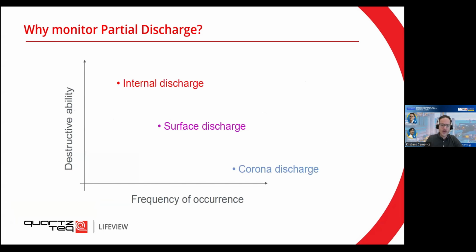So why do we need to monitor? The main reason here, as you saw before, is that for example the surface discharges, it's sometimes possible to spot some of them by eye, corona discharges as well. However, the most destructive are the internal discharges that are often hidden from the naked eye, so you cannot really see what is happening inside your machine, whether these discharges are present or not. So for that, you need to monitor them somehow, to know what is happening inside the machine, to know if you have these dangerous discharges.